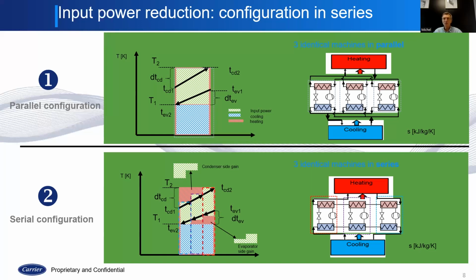Of course there are a lot of constraints, and it works only if the gradient of temperature, meaning the difference between entering and leaving, is large enough that this area becomes significant. Just for your information, data center is the case - we usually operate with 10 degrees C, or sometimes 12 degrees C difference.